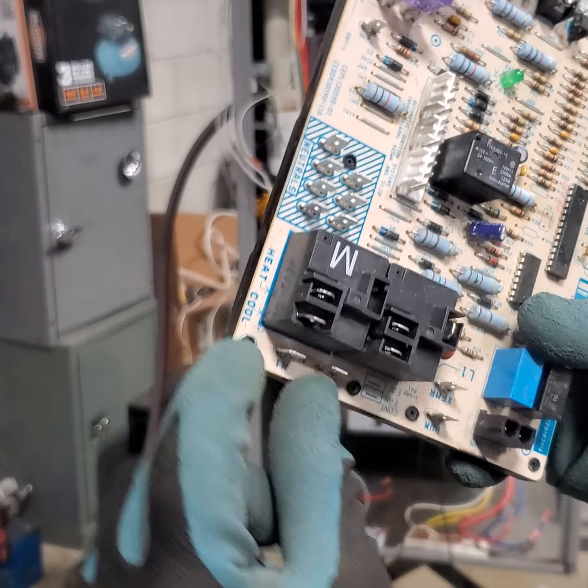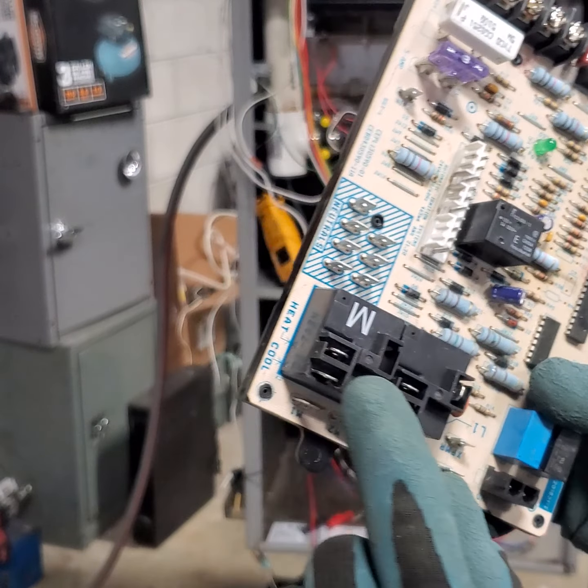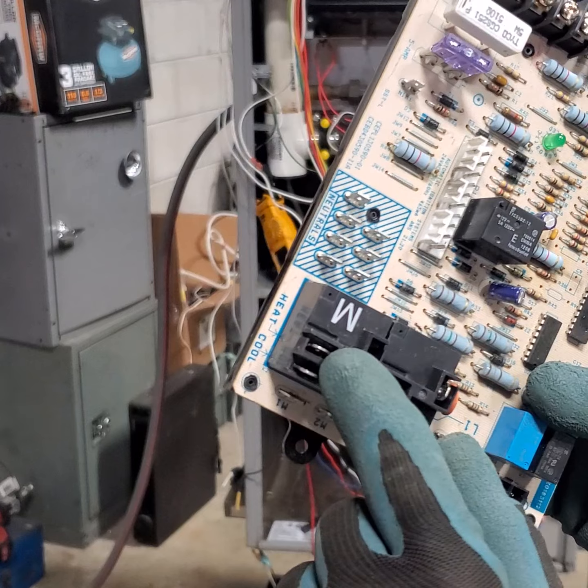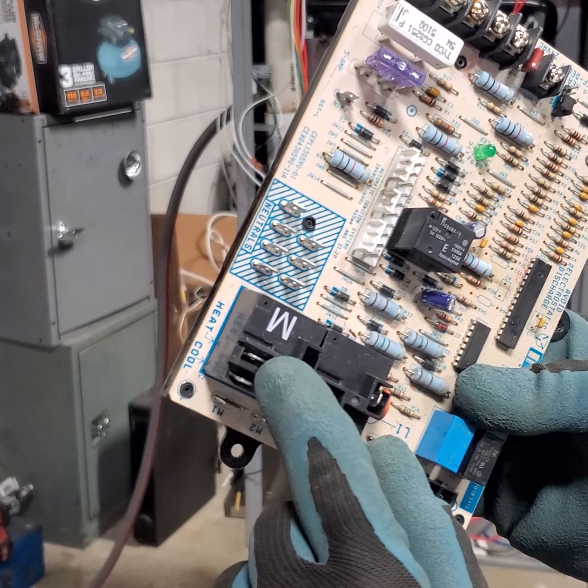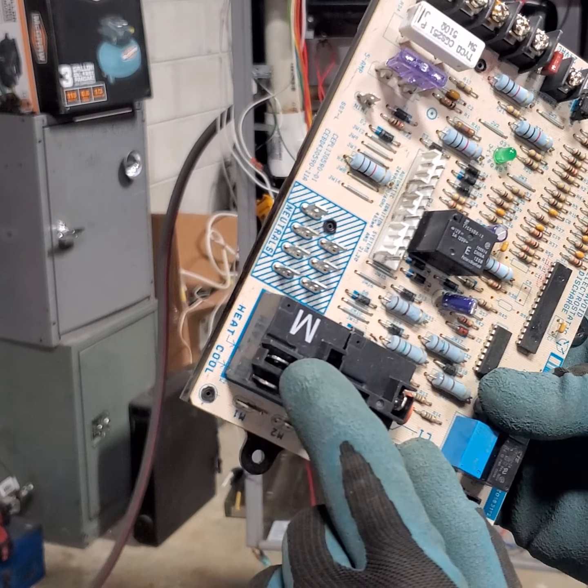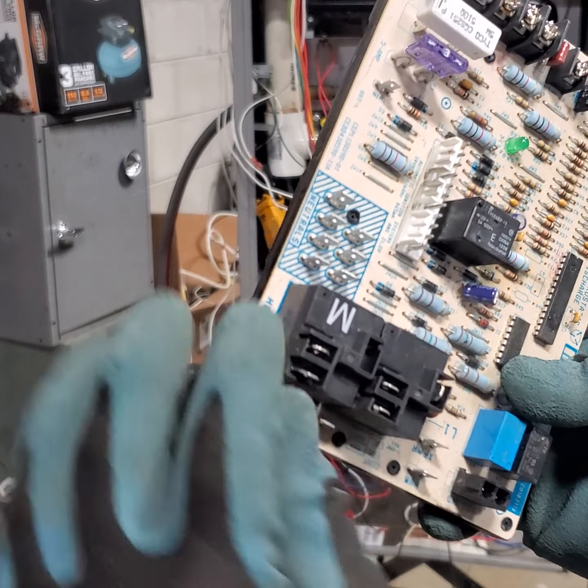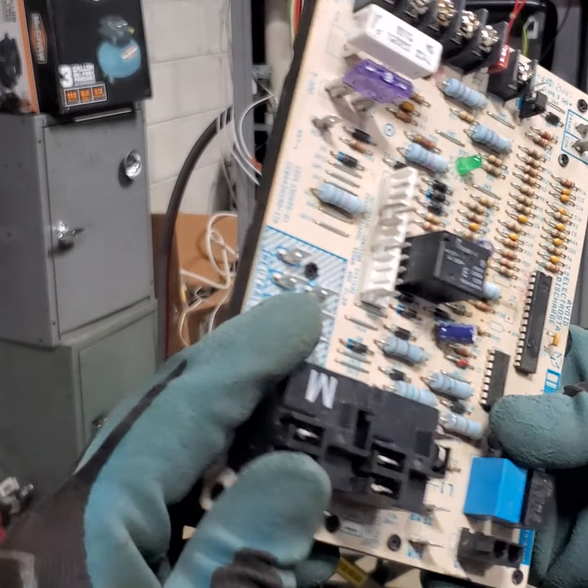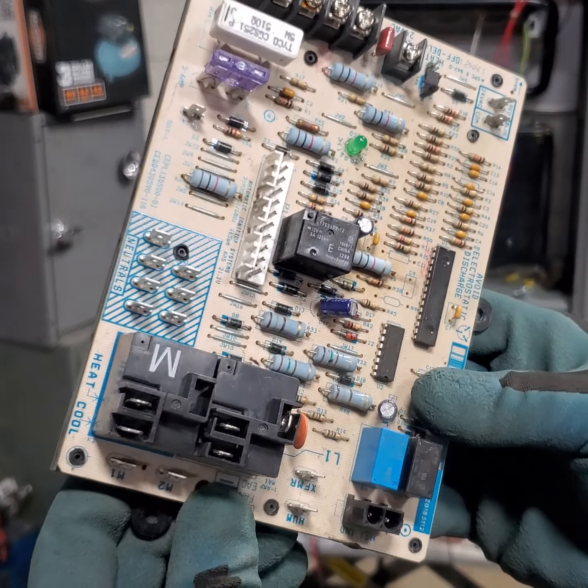And as you see, cool and heat, so here you can put any temperature. I usually use the red wire from the blower for low speed, and I use either the yellow or black wire, usually for higher speed.